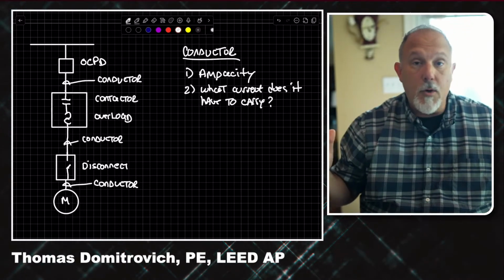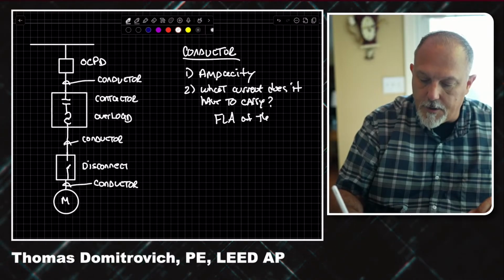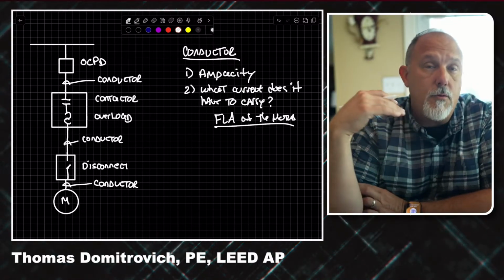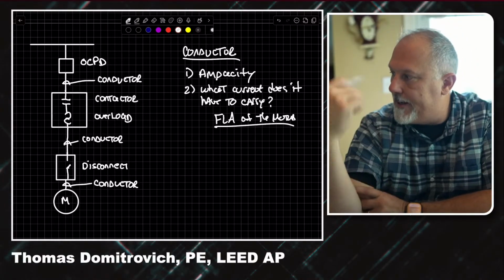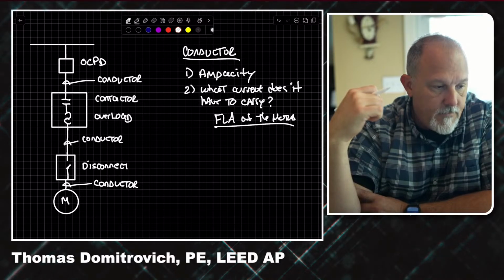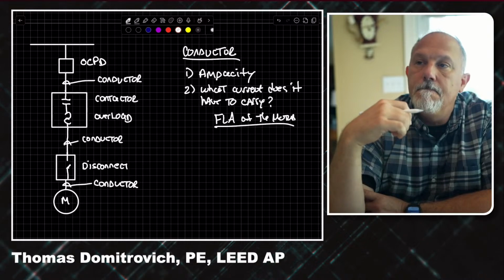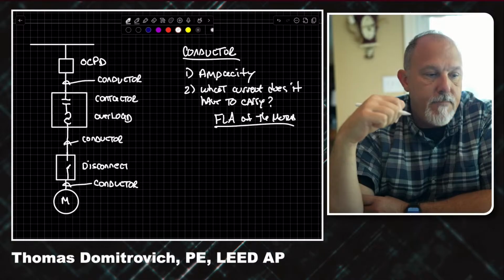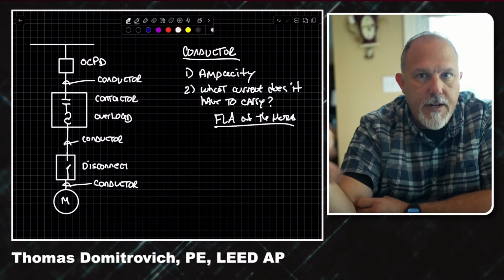Well, the motor current, right? The full load amps of that motor. I don't care if it's a continuous duty motor. I don't care if it is going to operate continuously. It's only going to operate like my pump does downstairs, only every so often when the water fills up a little bit. On the HVAC system, I have a pump down there on a dehumidifier. It puts the water in there, and there's a little motor in there that every now and then turns on.